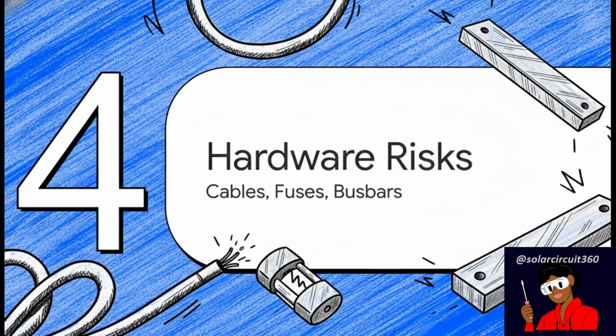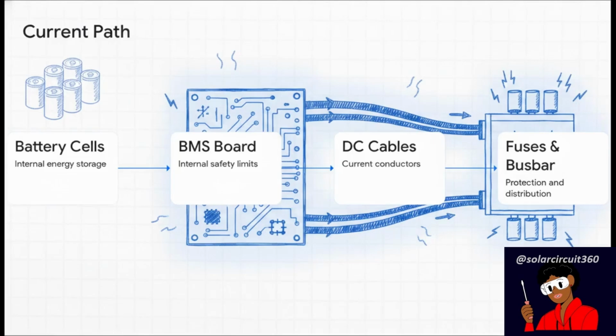Now let's trace that massive current outside the battery and look at external hardware risks, specifically cables, fuses, and bus bars. You've really got to think of your system like a literal chain. For your inverter to actually use those 231 amps safely, that current has to jump through a series of physical checkpoints without generating catastrophic heat. It has to flow from the internal battery cells, pass through the delicate BMS electronics, travel out through your DC cables, and finally cross over your fuses and bus bars.